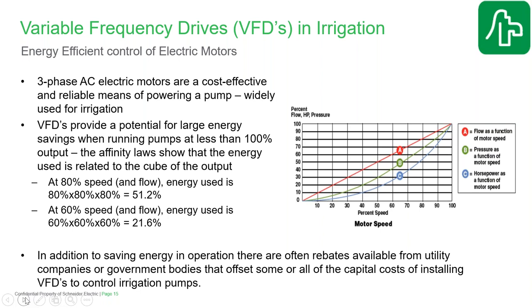A variable frequency drive allows you to directly control the speed of the pump and therefore the output of the pump. And this enables you to realize some very significant energy savings anytime you're not running at 100% output of a pump. The reason for that is to do with physics, and we're not going to spend the time today to go through exactly all the calculations and equations, but essentially the relationship between the energy used to run the pump and the speed, and therefore also the flow output of the pump, is a cube function.